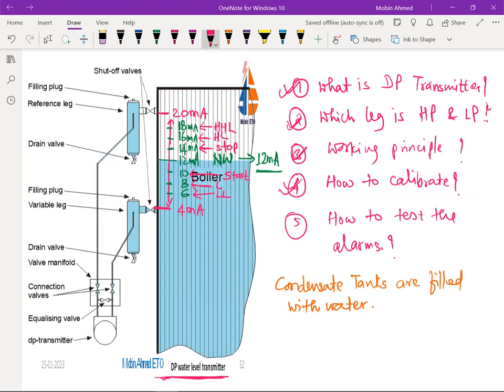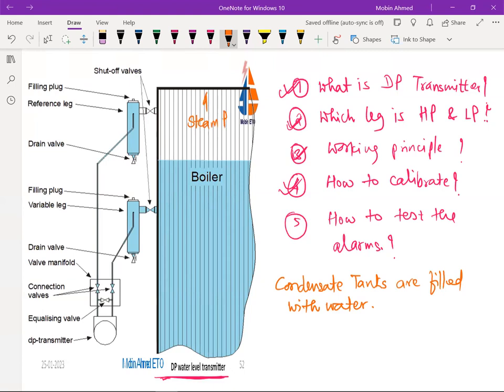First of all, by opening the drain, here you are going to close this set of valves, and by opening this drain, we should not carry out the test. If you are going to open this one, this side is going to be a high pressure, and this side there will be no pressure. Now remember, the steam is going to play a role here. Can you see the steam? Now suppose the steam pressure here, steam pressure is also there. This side, this side, this side, all the sides. Now here there is P reference plus P steam, and P steam is very, very high. Suppose if it is 8 bar, that is quite high.